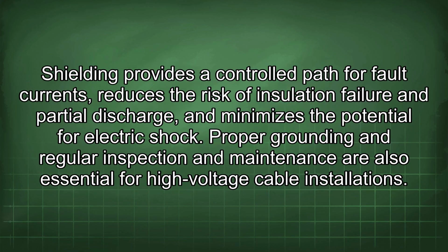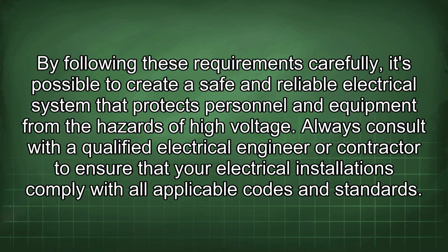Shielding provides a control path for fault currents, reduces the risk of insulation failure and partial discharge, and minimizes the potential for electric shock. Proper grounding and regular inspection and maintenance are also essential for high-voltage cable installations. By following these requirements carefully, it's possible to create a safe and reliable electrical system that protects personnel and equipment from the hazards of high voltage.